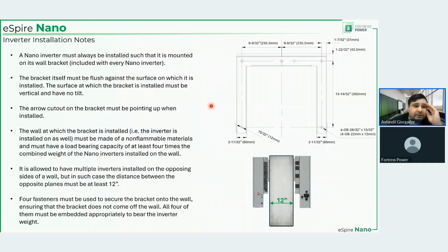Now, a couple of other notes about the installation. As I said before, only wall mounting is the acceptable way of installing this inverter. It cannot be floor mounted. It must be vertical at all times, so it should not be tilting, inclining, or anything like that. The wall that you install the inverter onto should be able to support 4 times the weight of the inverter or inverters that you are installing onto this wall. The wall obviously has to be made of non-flammable materials. You can have multiple inverters on the opposite sides of the wall, but the previous 2 conditions remain true. So 4 times the combined weight of the inverters, and non-flammable material. But there's also one addition: the width of the wall should be no less than 12 inches.